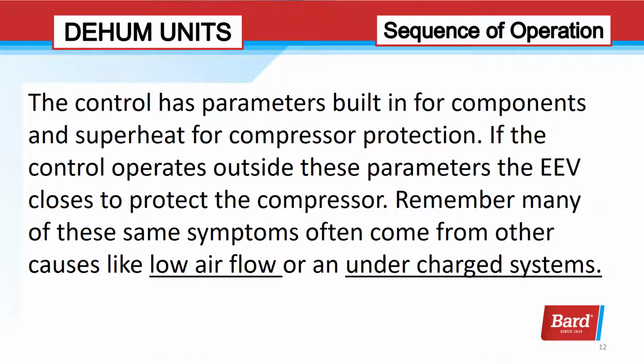The control has parameters built in for components and superheat for compressor protection. If the control operates outside these parameters, the EEV closes to protect the compressor. Remember, many of these same symptoms often come from other causes like low airflow and undercharged systems.